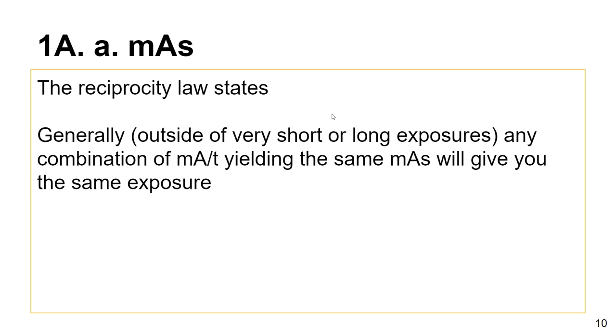The reciprocity law says that any combination of mA or time should give you the same intensity of radiation. If you double the mA and halve the time, you're back where you were with the same intensity. That's why it's also good to be able to cut time and increase mA.